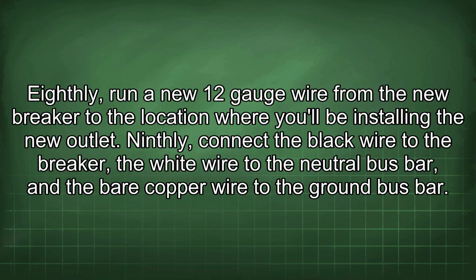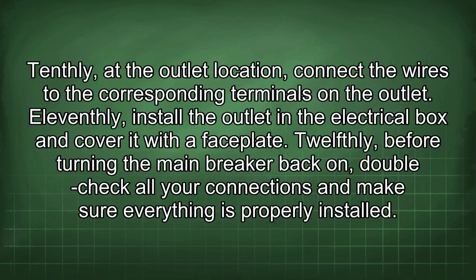Eighthly, run a new 12-gauge wire from the new breaker to the location where you'll be installing the new outlet. Ninthly, connect the black wire to the breaker, the white wire to the neutral bus bar, and the bare copper wire to the ground bus bar. Tenthly, at the outlet location, connect the wires to the corresponding terminals on the outlet. 11thly, install the outlet in the electrical box and cover it with a faceplate. 12thly, before turning the main breaker back on, double check all your connections and make sure everything is properly installed.